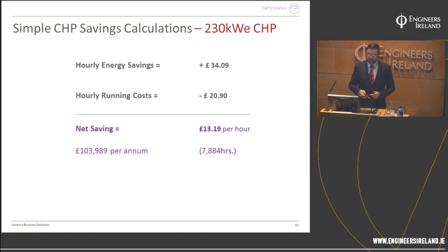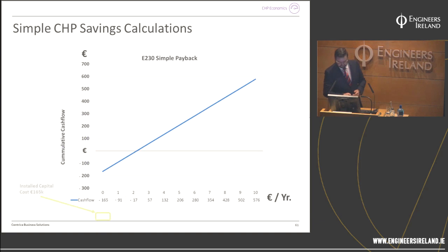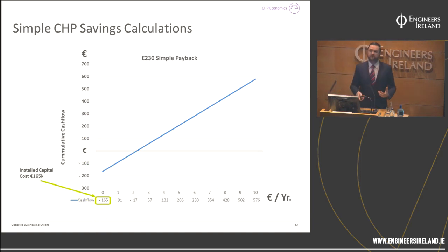And actually, my next few slides might add to this as well, because this is a very simple calculation we're doing here and a very simple payback. This was a hospital in the UK where they already had a 230 kilowatt electrical CHP installed. That was removed and a new one was put in, so we knew exactly what was needed here. The installation costs were very low - you could see here, 165,000. So the payback in this for the NHS was fantastic. And actually, in today's world, they're always looking for a payback of about 3 years and less.